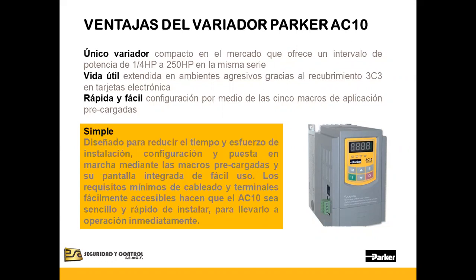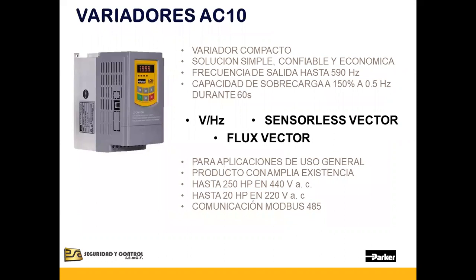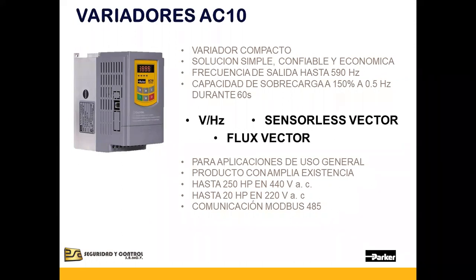Julio Sánchez de Parker comenta que el AC10 no maneja flux vector, solamente los dos primeros modos. Existen tres formas de control: voltaje-frecuencia, sensorless vector y flux vector. El AC10 incluye los primeros dos —volt por hertz y sensorless vector— pero no así flux vector, que está disponible en el AC30 y en el 890. Volt por hertz y sensorless vector cubren el 90% de las aplicaciones que podemos encontrar en la industria.